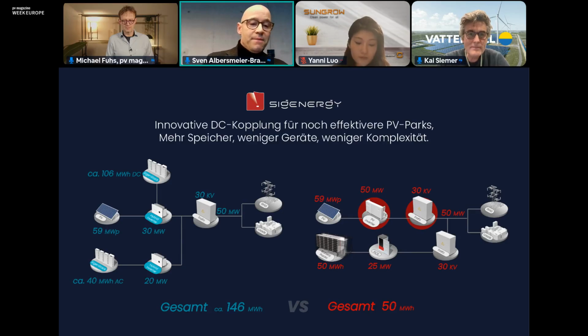Here we are. One of the bigger advantages of a DC coupled system is, of course, that we can save the resource grid connection, because grid connection is one of the critical parts in big solar installations. By DC coupling, you can more or less divide the grid connection needed by half compared to an AC coupled system, because usually grid operators would consider the AC coupled storage as being just a second generator that potentially can also discharge to the grid with the same power as the solar installation.